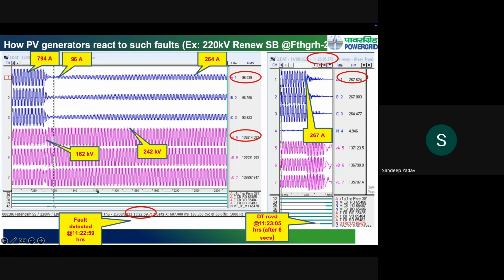If you look at the time scale, even after 2.5 seconds, the current has not reached its pre-fault level. The Indian grid code says that in case of a fault, generators are allowed to reduce their active power, but that active power should come back to 90% of the pre-fault power within 1 second. So if the pre-fault power is 300 megawatt, within 1 second of the fault it should come back to 90%, which is 270 megawatt. However, in this case, even after 2.5 or 3 seconds, the generator has not reached its pre-fault power level, which is against the grid code; this particular generator is not meeting the requirements. And these are the early days, 2021, 2022.